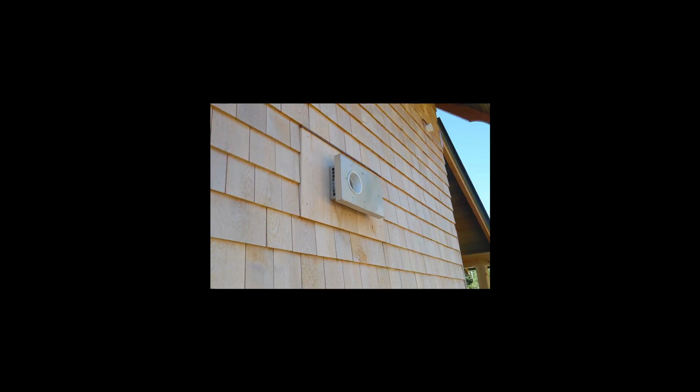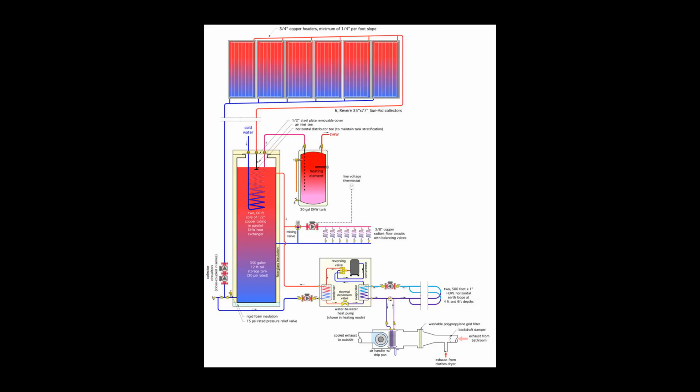Classification. Following the work of IEA SHC Task 26, 1998 to 2002, solar combisystems can be classified according to two main aspects. Firstly, by the heat, or cool, storage category, the way in which water is added to and drawn from the storage tank and its effect on stratification. Secondly, by the auxiliary heat, or cool, management category, the way in which non-solar thermal auxiliary heaters or coolers can be integrated into the system, maintaining stratification. The variation in water temperature from cooler at the foot of a tank to warmer at the top is important so that the combisystem can supply hot or cool water and space heating and cooling water at different temperatures. A solar combisystem may therefore be described as being of type B, DS, CS, etc. Within these types, systems may be configured in many different ways.